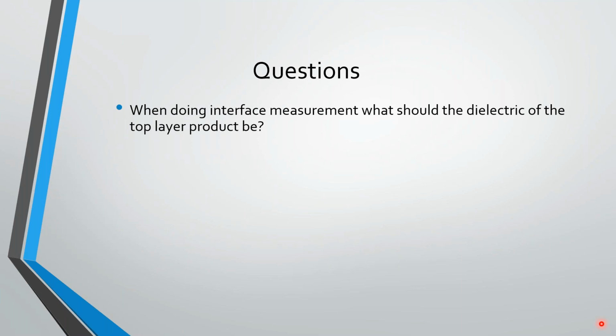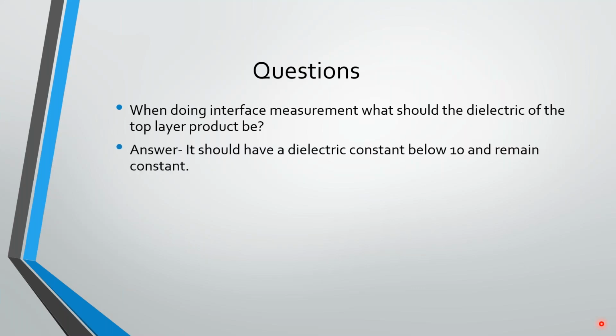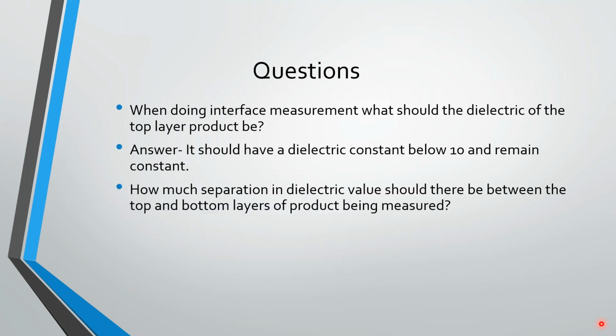When doing an interface measurement, what should the dielectric of the top layer product be? I didn't give a specific number, but said it had to be below a certain value - that number should be below 10. The top layer of what we're trying to measure should have a dielectric constant below 10, and we'd like it to remain constant, not fluctuating with temperature, etc.